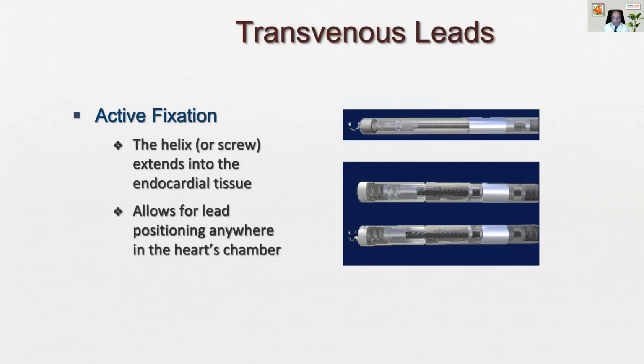The one disadvantage in the initial experience was that of perforation, because this lead is more susceptible to cause perforation. But that problem has been taken care of, because we now know that it can happen. So most of the operators are very careful, and generally when we screw, we do not extend the stylet right up to the tip. So we know how to take care of the problem of perforation.